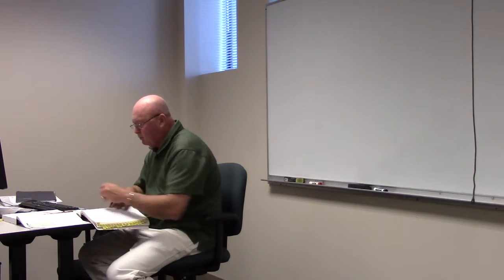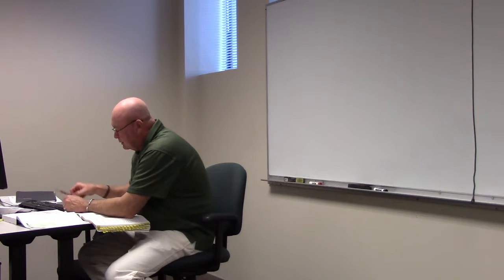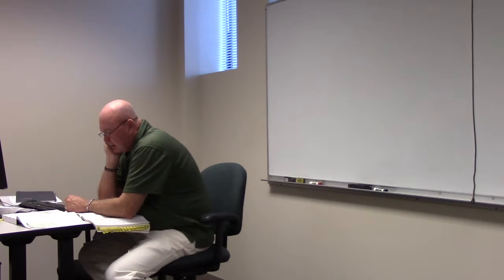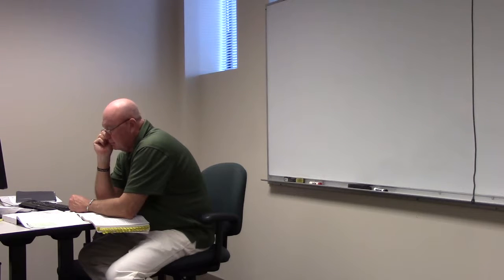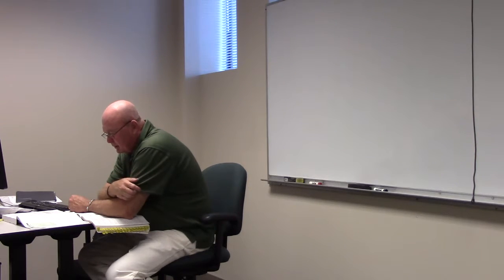All right, 3.1.0, commercial and industrial lighting loads. So we're going to do lighting first. First thing, lighting. We were just talking about that. Type of occupancy determines the method employed to calculate loads. Industrial and commercial buildings, two of these categories. Standard calculations used to compute the load and determine the service equipment. Requirements are arranged differently from those on dwellings. There are specific types of loads that must be considered. Let's kind of look at some of this.